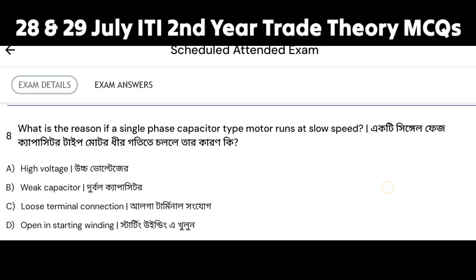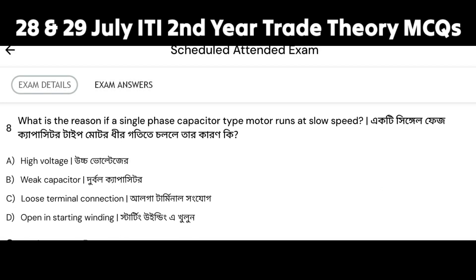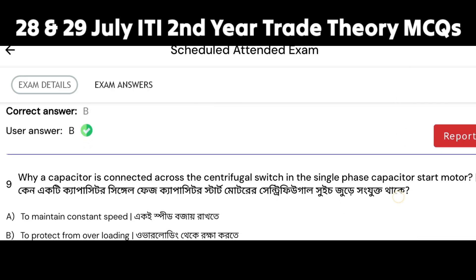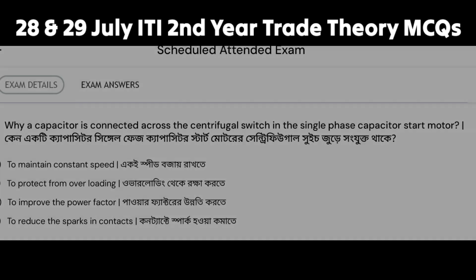What is the reason if a single-phase capacitor type motor runs at very low speed? The options are: high voltage, weak capacitor, loose terminal connection, and open in starting winding. Here we have to say the single-phase capacitor motor running at low speed — option B, weak capacitor, is the correct answer.